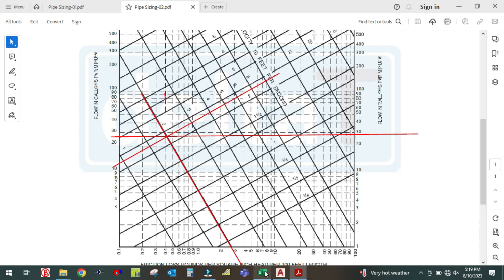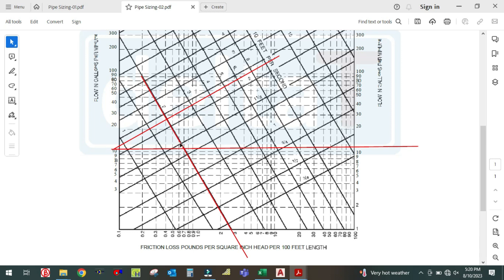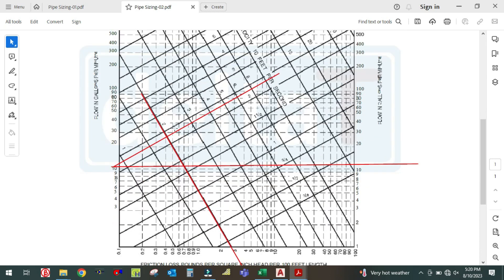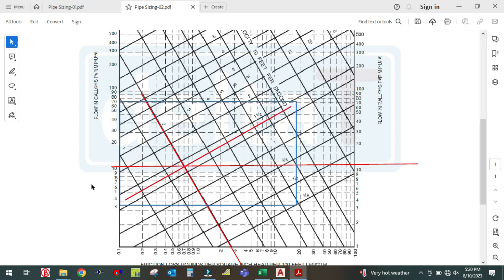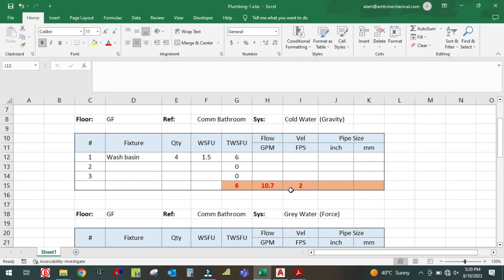Plot the values on the chart. Your GPM is 10.7, so move the line to approximately 10.7. Then find the velocity line at 2 feet per second. Where these two lines coincide — that is your pipe size. The nearest diameter line is 1.5, so your pipe size will be one and a half inch.